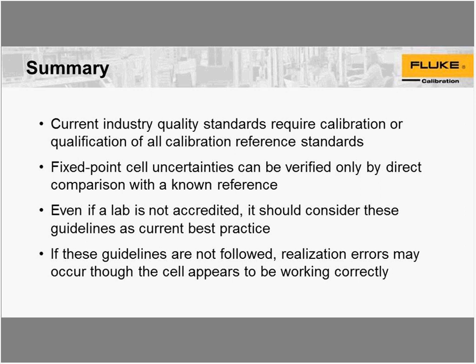Industry quality standards require calibration or qualification of all different standards, fixed point cells included. Fixed cell uncertainties can be verified in comparison with a known reference. Even if not audited, we recommend that these guidelines be followed because they do represent current industry best practice. And if these guidelines are not followed, we demonstrated some of the errors that can happen, some of them very difficult to detect, and interfere with the fixed point cell's uncertainties.